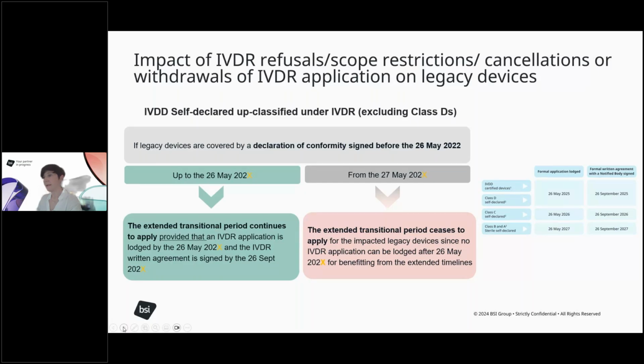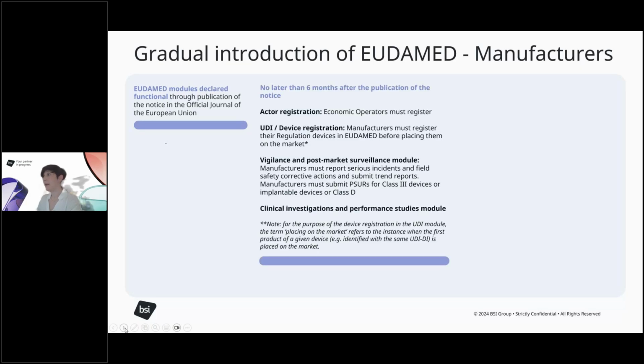So then, in terms of the gradual introduction of EUDAMED, key will be the date when the notice of functionality of a certain module will be published on the Official Journal of the European Union. From that date, the regulation allows for a 6-month transition period, meaning that no later than 6 months after the publication of the notice of the actor module, the economic operators must register. After the publication of the notice for the UDI device module, manufacturers must register their regulation devices in EUDAMED before they place them on the market.